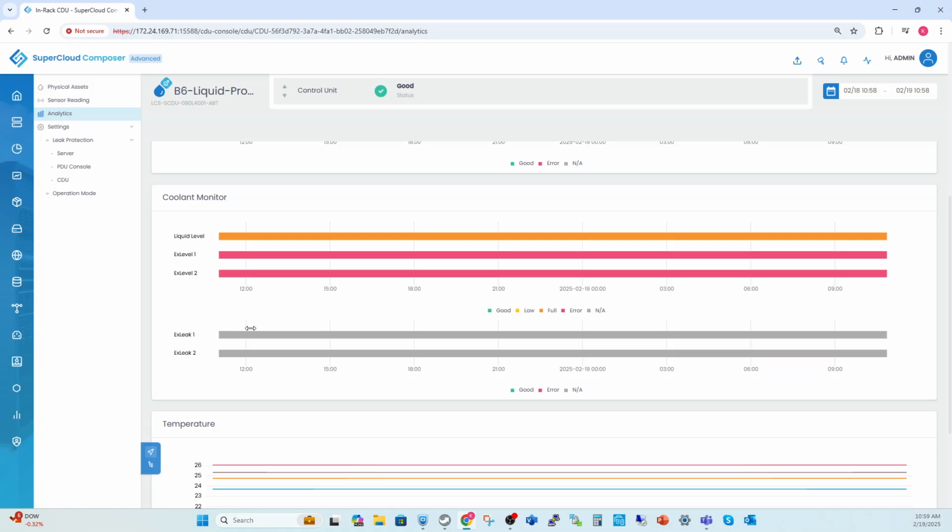And the other use case or scenario is, what if there was a sensor leak associated with a cold plate? The BMC takes that action. It has jurisdiction about shutting down that server. And then we, as an SCC, report on that action. We don't set the enforcement action or policy. And we'll get into detail later of how you set this enforcement action in the event that there was a leak.